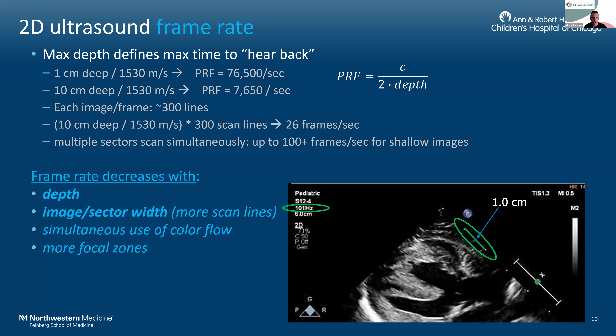So this is the first trade-off that defines the practice of echo. The deeper the image, the less frequently scan lines can be sent and detected. And similarly, the more scan lines you have, or the wider the sector, the lower the frame rate. So echo image optimization is all about getting the most useful images while dealing with the trade-offs that are consequences of physics.